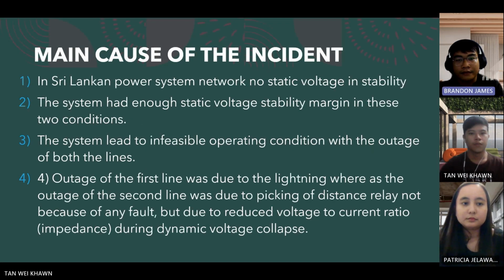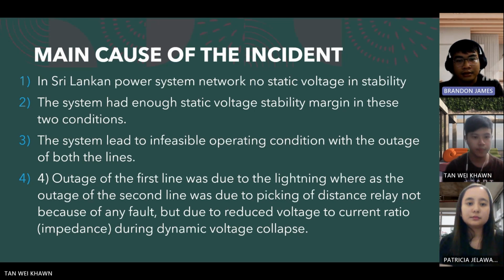Next, the main cause of the incident. Firstly, in the Sri Lanka power system network there is no static voltage instability. Second, the system had enough static voltage stability margin in these two conditions. Third, the system led to an infeasible operating condition with the outage of both the lines. Fourth, the outage of the first line was due to the lightning, whereas the outage of the second line was due to picking up of the distance relay, not because of any fault, but due to the reduced voltage to current ratio, impedance, during dynamic voltage collapse.